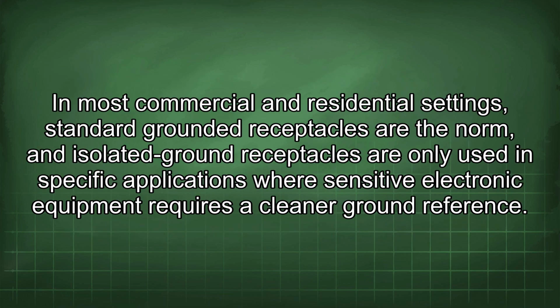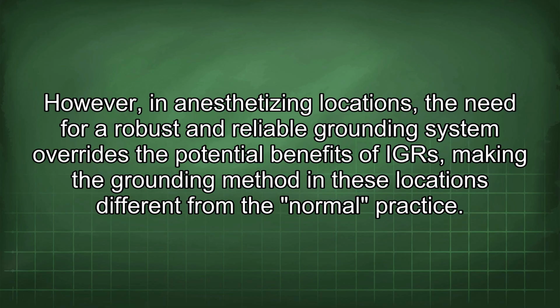In most commercial and residential settings, standard grounded receptacles are the norm, and isolated ground receptacles are only used in specific applications where sensitive electronic equipment requires a cleaner ground reference. However, in anesthetizing locations, the need for a robust and reliable grounding system overrides the potential benefits of IGR, making the grounding method in these locations different from the normal practice.